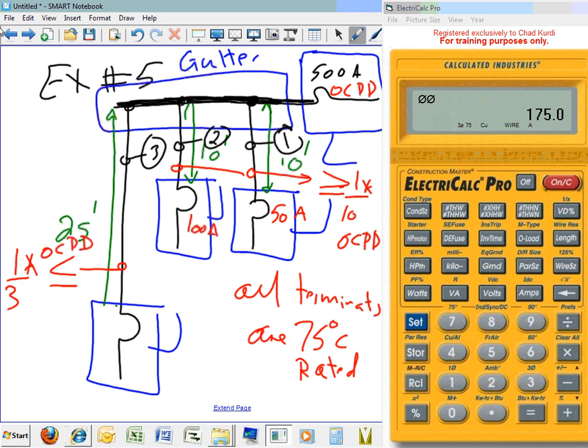Thank you. You said we should be assuming the temperature to be 75 when you tap. If you're doing taps with gutters, 99% of the time the conductors, the gutters, the lugs, everything is rated for 75. If you don't know though, you use the rule of the code. What's the rule? 100 or less, 60; more than 100, 75. That's kind of a cover-your-bottom type of rule. Okay, thank you guys.